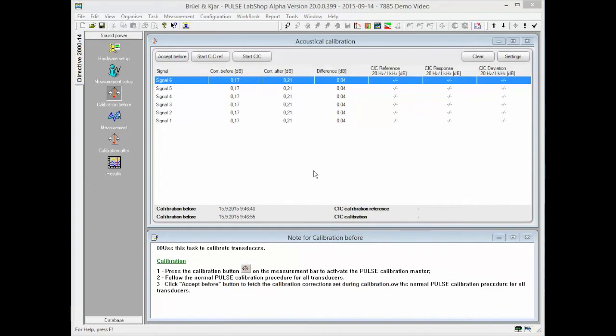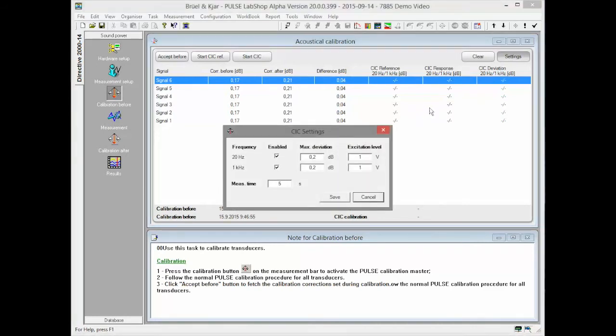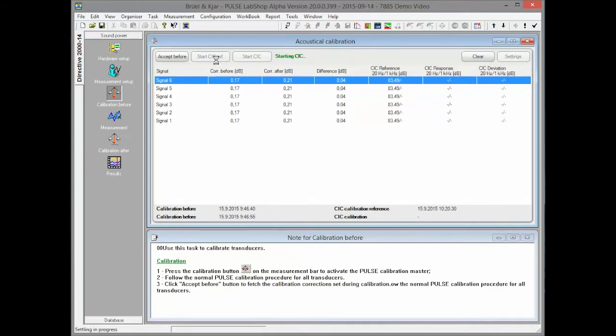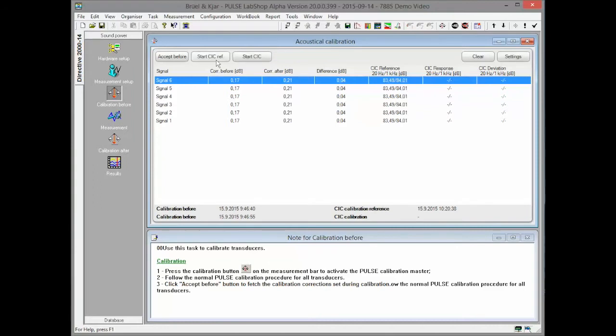In addition to acoustical calibration, 7885 allows for performing a CIC calibration. The CIC calibration can be performed at 20 Hz and 1 kHz. The excitation level, measurement time and maximum deviation can be conveniently set in the calibration settings. The reference CIC response is measured by clicking the button Start CIC Ref. The response is measured at selected frequencies automatically.